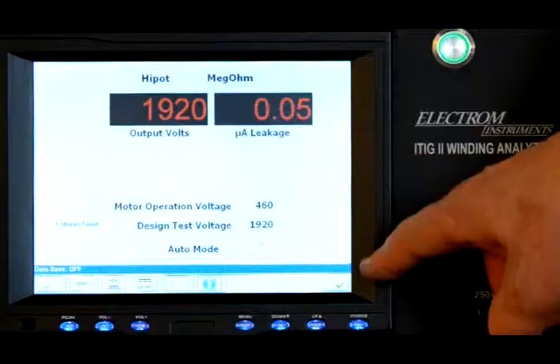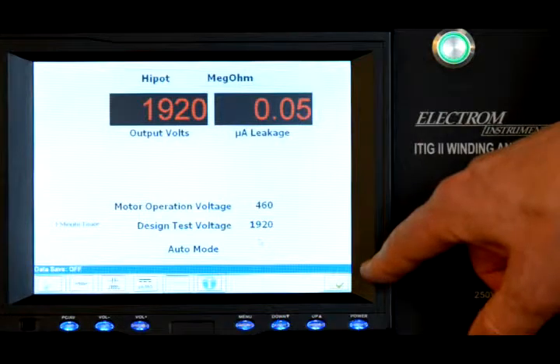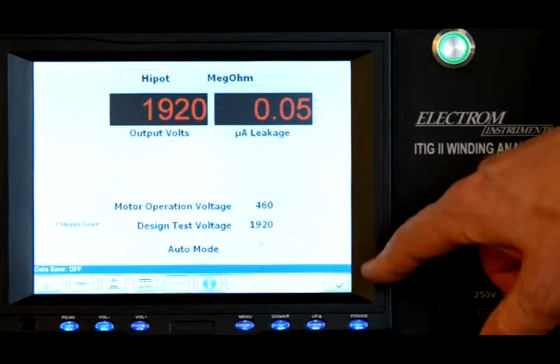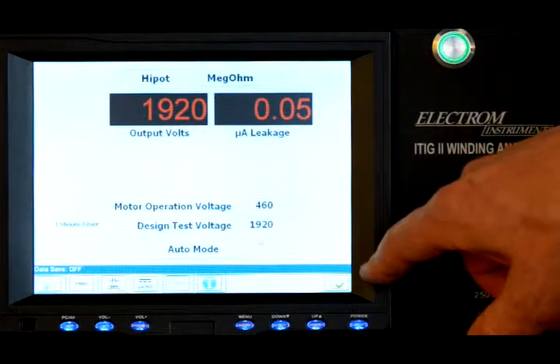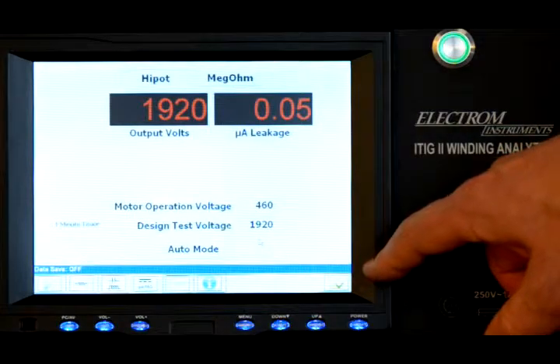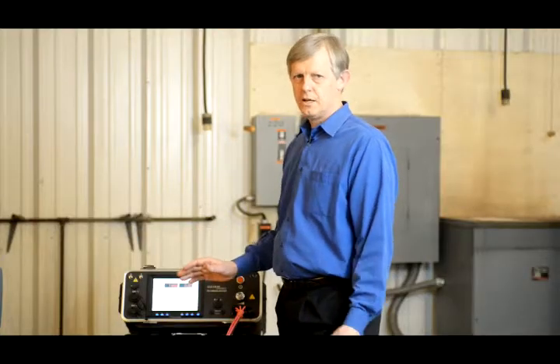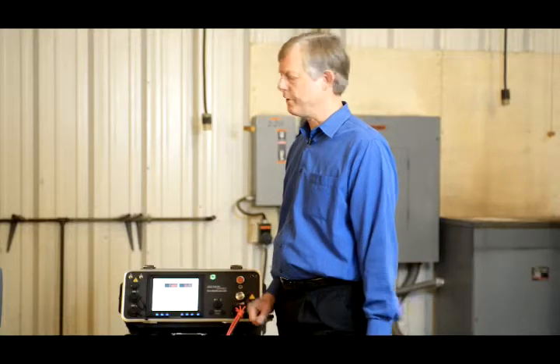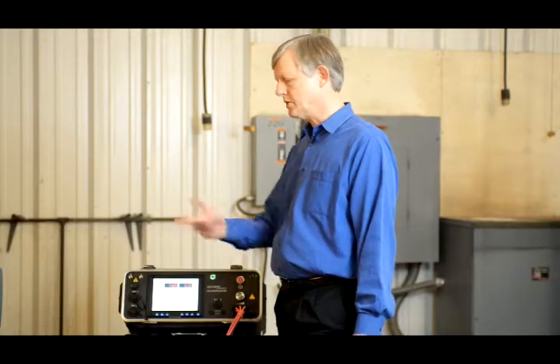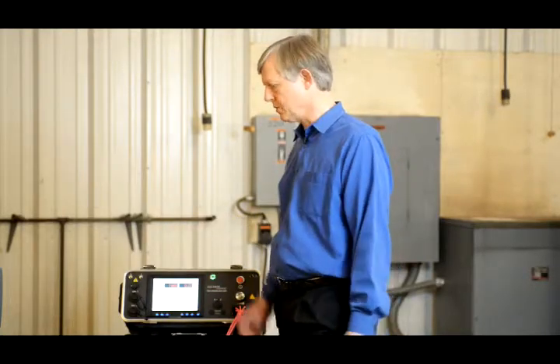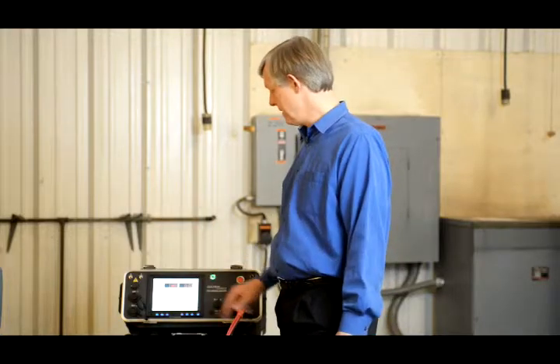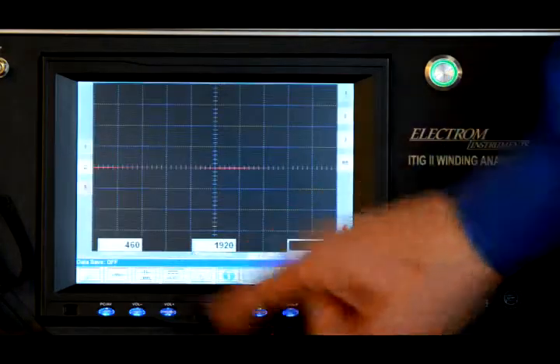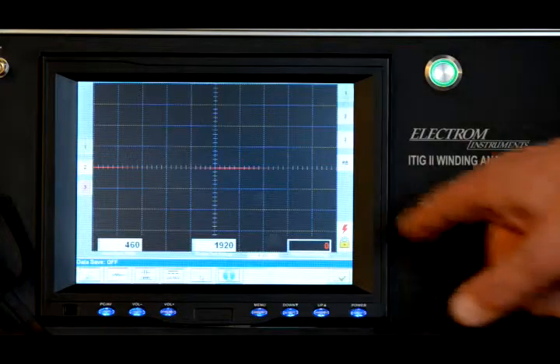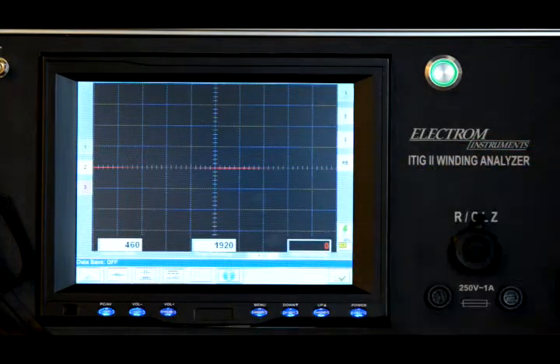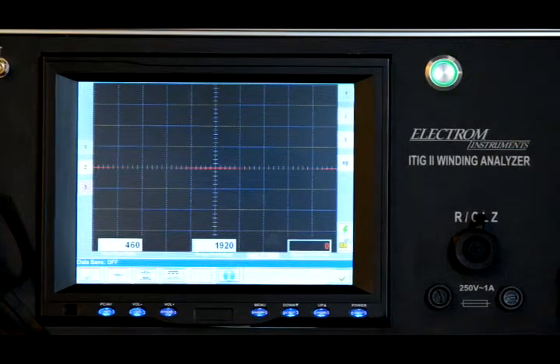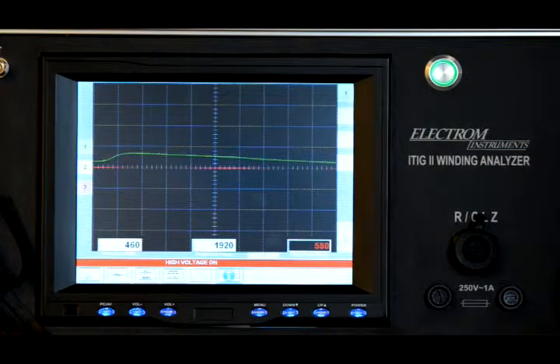You may have noticed that this message line down here turned when I shut the test off. It indicates what the voltage in the windings is and tells you when it's down to basically 0 or below 30 volts, so you can safely go and remove the leads or touch the motor. The last test is the surge comparison test. We automatically start with lead number 1. We unlock it to start the test.